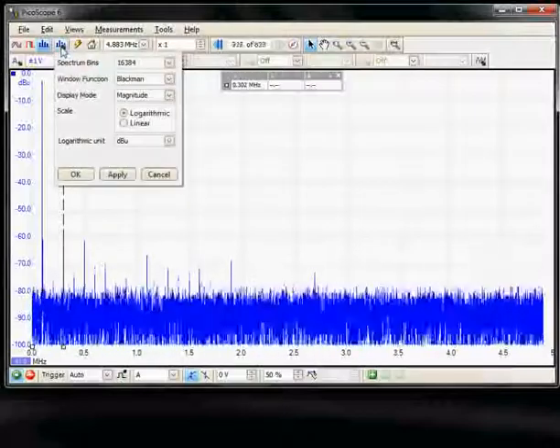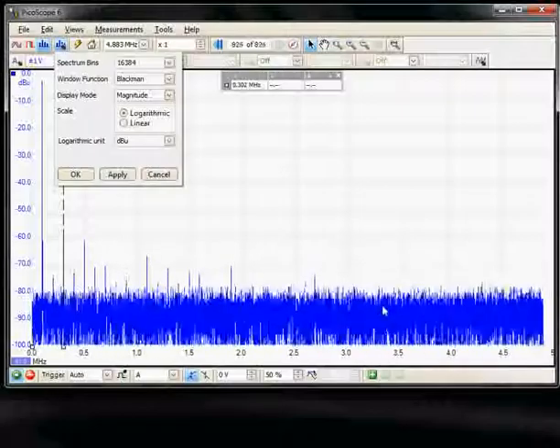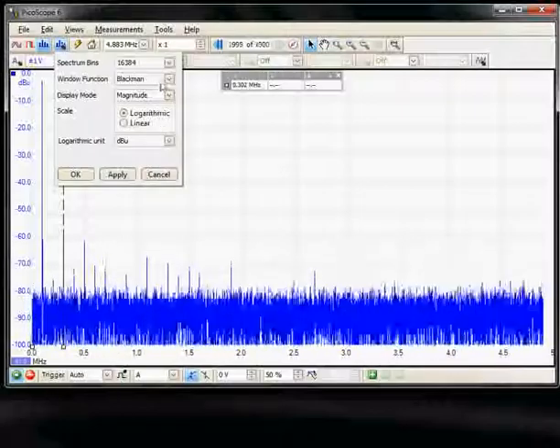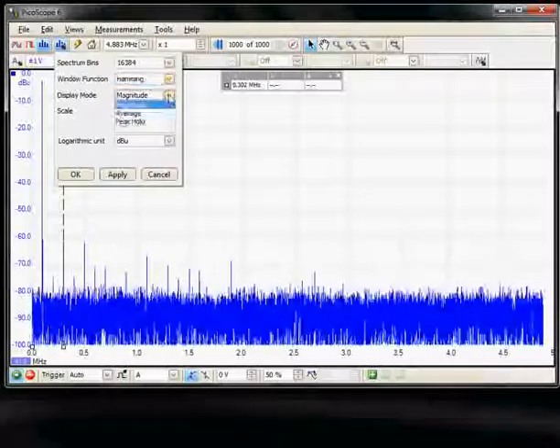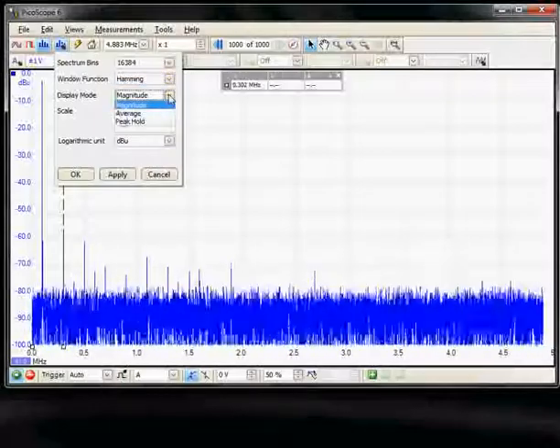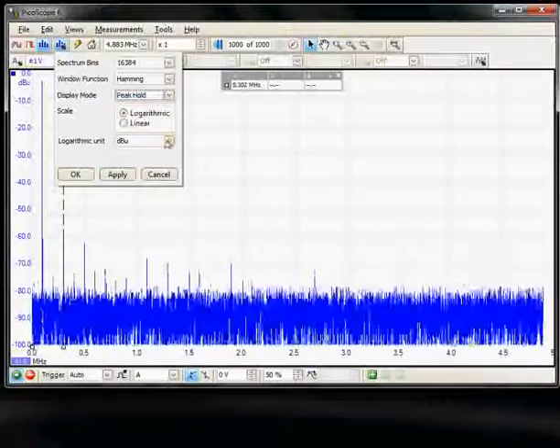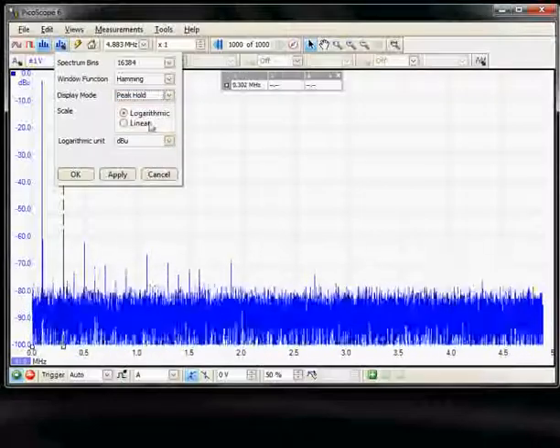The next menu item is the setup options for the FFT. We can define the number of bins that the data is acquired into and we can change the window functions and the display mode to magnitude, average, and peak hold. We can change the vertical units and the scale factors to log and linear.